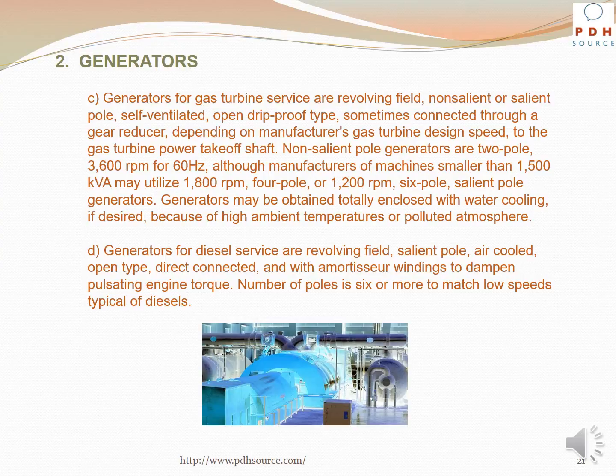Generators for diesel service are revolving field, salient pole, air-cooled, open type, direct connected, and with amortisseur windings to dampen pulsating engine torque. Number of poles is 6 or more to match low speeds typical of diesels.